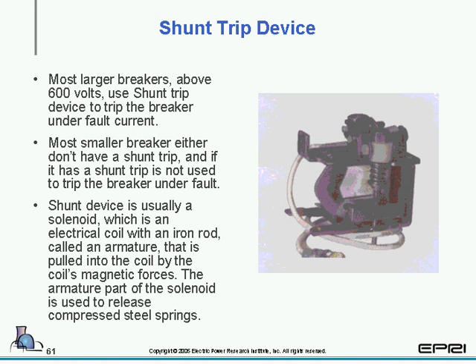Now the trip coil on most large breakers is used as a shunt trip device to trip the breaker under fault conditions as well as normal conditions. Unlike most smaller breakers, which either don't have shunt trips, or if they have shunt trips installed, they are used to trip the breaker under non-fault conditions or normal operations. And we have a definition of what a shunt trip device does. It's an armature wrapped around a coil that, when a magnetic field is applied, will draw the armature in and trip the breaker.